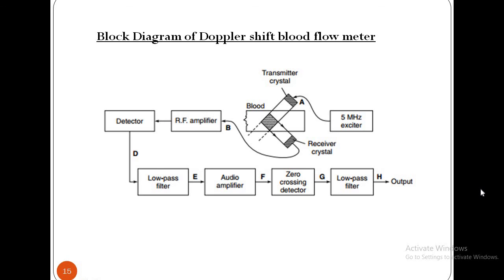The detector produces a sum and difference of the frequencies at B. The low pass filter selects the difference frequency resulting in audio frequencies at E. Each time the audio wave crosses the zero axis, a pulse appears at G. The filtered output level at H will be proportional to the blood velocity.